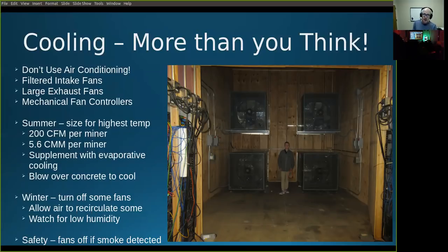So my rule of thumb is for the heat of summer, about 200 cubic feet per minute per miner. And we haven't had to supplement with evaporative cooling.